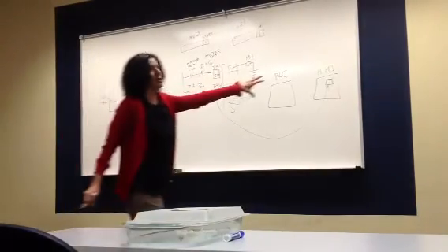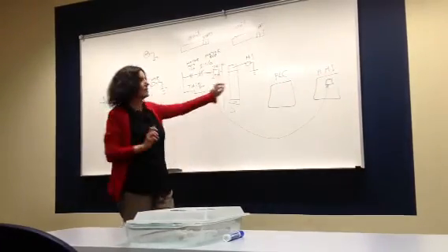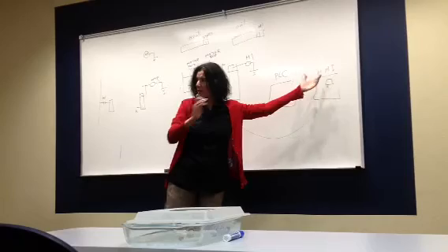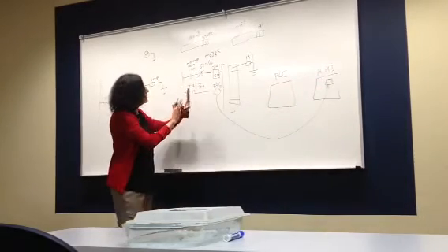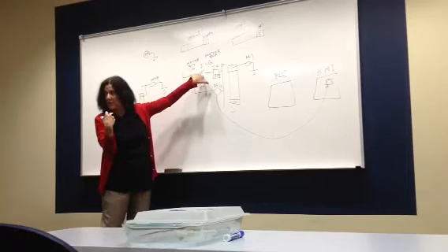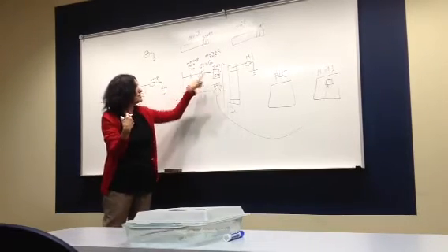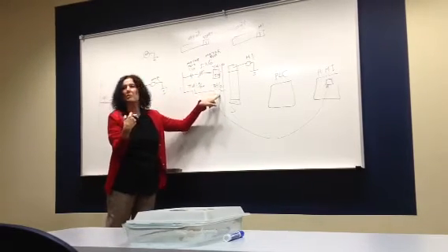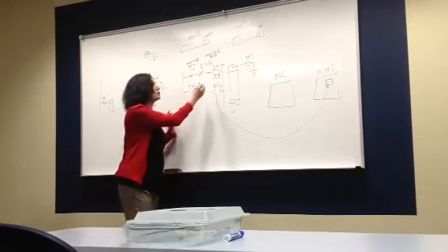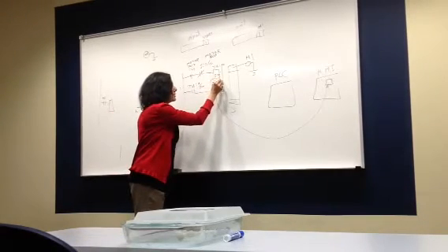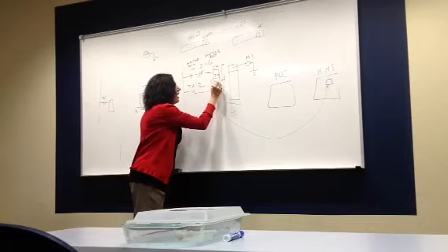You can flash it in the HMI, or you can use the two timers I told you about to send the bit flash, and then they acknowledge it. But this is the real story. If the output is true and I don't receive the input from the magnetic starter in 5 seconds, the done bit is true and B3/ should tell me failed to start. Failed to start. That's in the test.